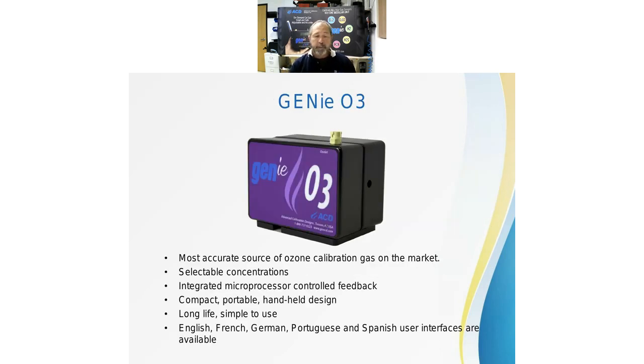Speaking of the ozone unit, the source, instead of being a galvanic cell, is a lamp. So every 100 hours of use, this unit will tell you to send it in to get it recalibrated. But if you've done much calibrating, 100 hours of cal gas is a lot of calibration gas. So with this one, you can select the output. The range is 0.2 to 1 liters per minute. We have English, French, German, Portuguese, and Spanish user interfaces, so you can select the language it's in. We get at least 500 hours of calibration gas out of this unit. And so it's a really long-lasting calibrator.